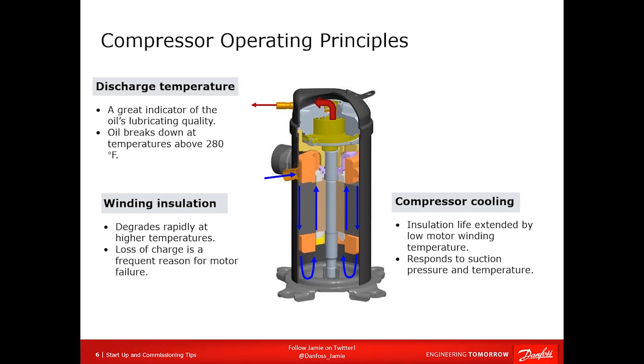So we spoke about things that are necessary for the components to have a good life. Well, let's look at the compressor. A compressor is very happy if it's cooled properly. The suction gas coming back flows over the compressor windings. They remove heat. This means that when the actual suction gas goes into the compression area, it's a lot hotter than when it went into the compressor. A lot hotter. And the hotter it is, the higher your discharge temperature is going to be.